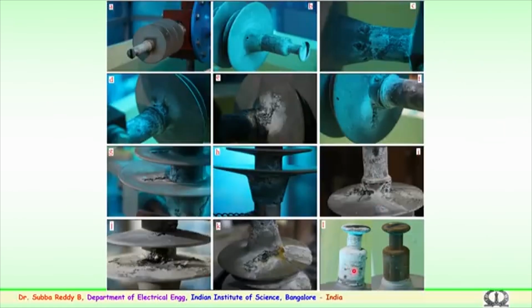Various types of changes, such as color indications, corrosion indications, failures, punctures, or surface degradation at various levels, were noticed in the experiments conducted for AC and DC applications, for both the normal contaminant as per the standard and the acidic contaminants, which are based on data obtained from acid rain conditions.